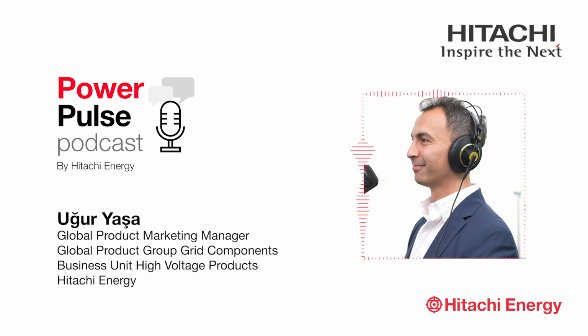Therefore, roughly 30 years ago, we invented a new technology called active filters. That's power-electronic-based technology with some sophisticated software on it that can actually filter harmonics at different harmonic frequencies, make power factor correction, and also some voltage balancing. Today we have a full-fledged portfolio for active harmonic filters and are still in the market leader position for this technology.